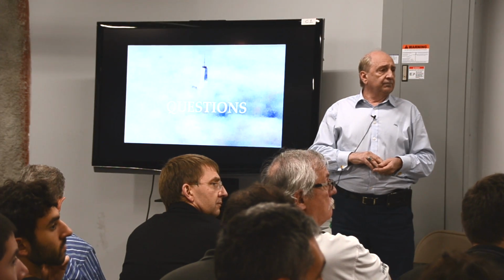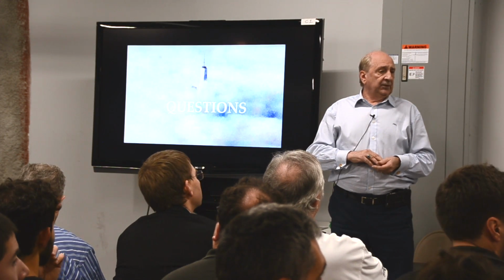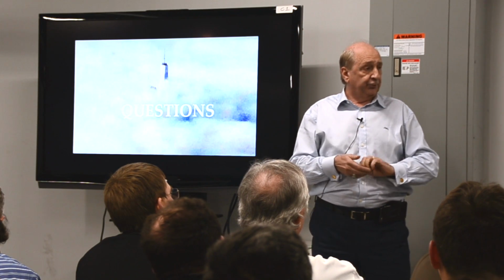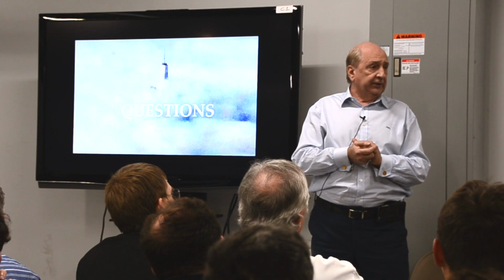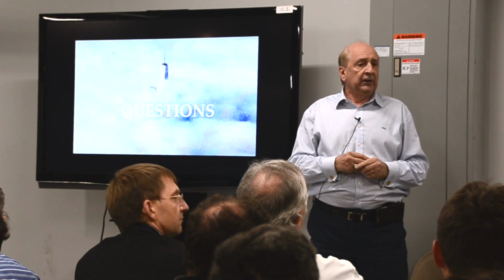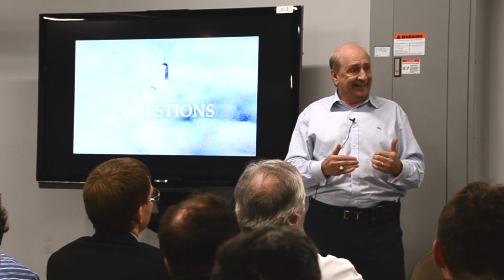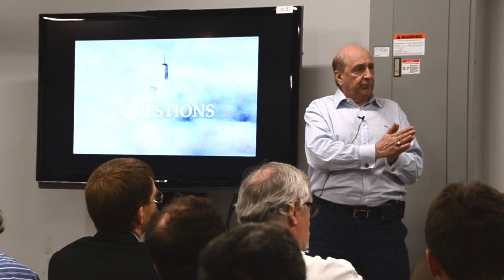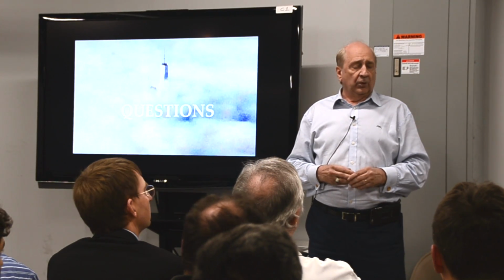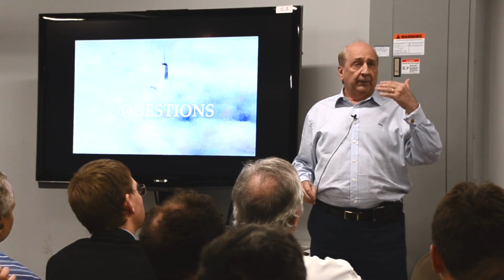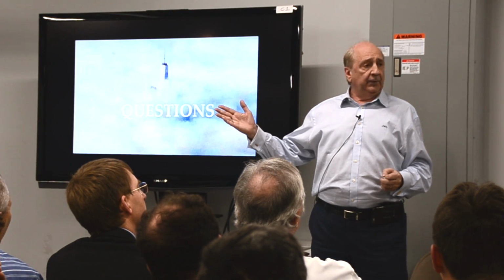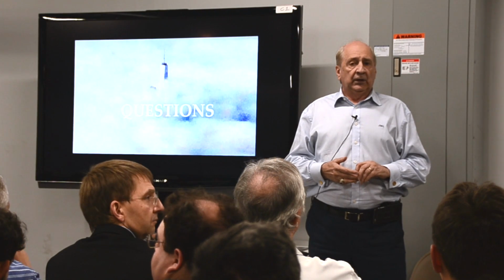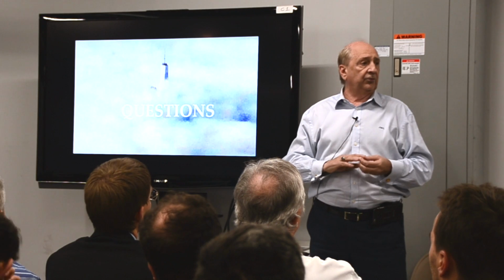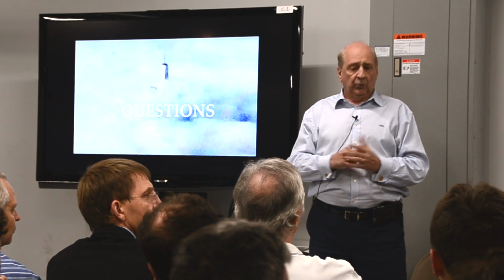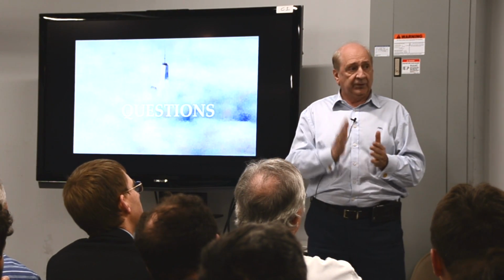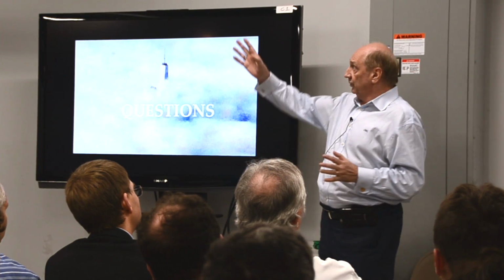Question: can you talk about the design plans, why you picked this floor specifically, and how much choice you had as the building was going up? When the MTVA group was dealing with the Port Authority pre-2008, they had the 89th and 90th floors set up for broadcast, so those floors were actually poured to handle the heavy transmitter load. When the Durst family got involved with the Port in 2010, we realized we didn't need demised rooms, individual spaces, or individual air conditioners for everything. It was more opportune to do a single open floor, which made for better air handling and electric facilities. With everything now IP-based and password protected, the security issue isn't like it once was—you're not going to have people up here fiddling around. As I said earlier, there's biometric and card readers on every door affecting anything secure for broadcast, so we know when somebody enters and leaves the space. And there are cameras in a few discrete places as well.